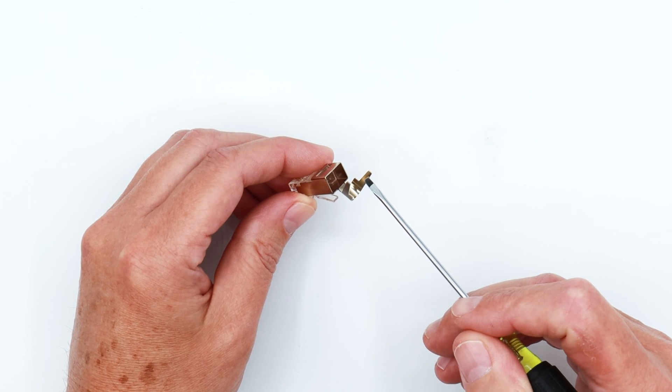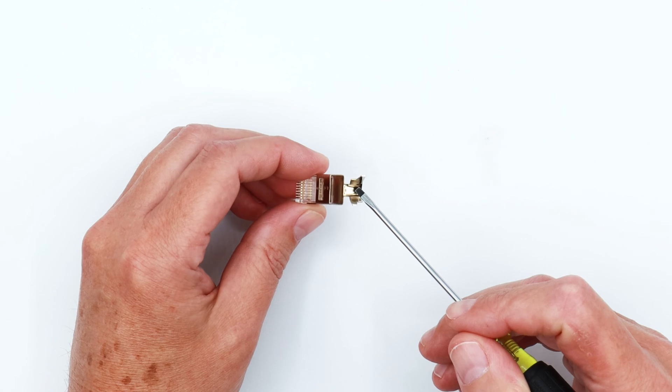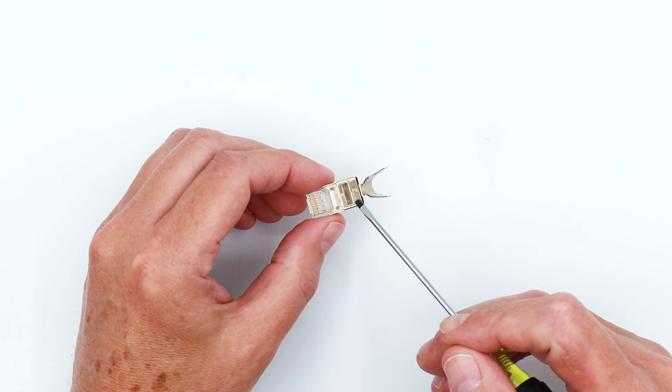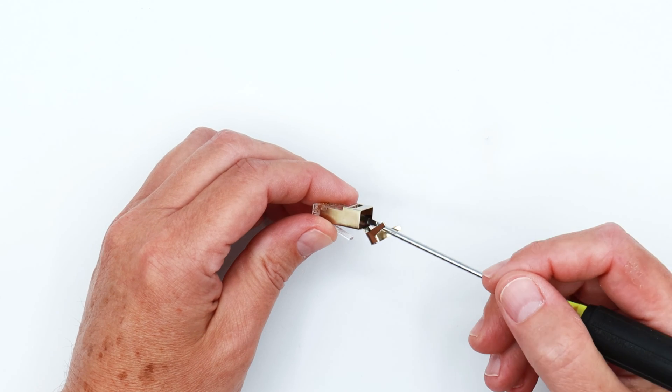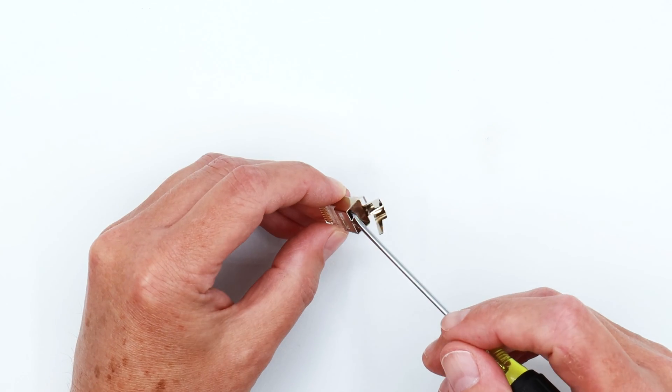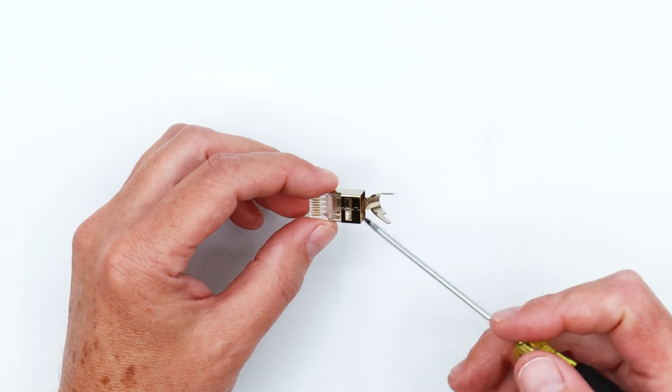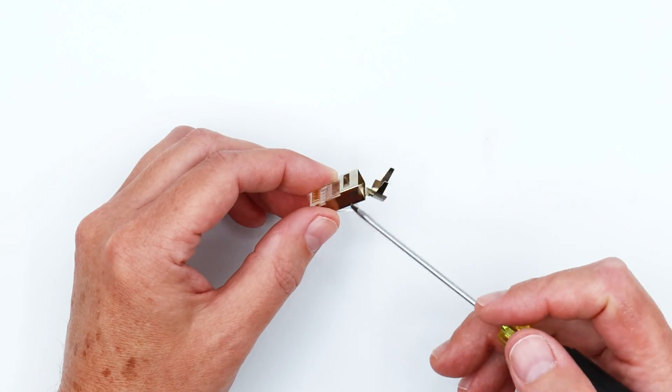The strain relief functions more at, well, I should say the external ground tab functions more as a strain relief for this particular plug because you can do the bonding on the inside because there's metal here rather than having to worry about bonding out here. So that makes it very versatile. There's lots of different ways to get the cable shield bonded to the hardware.